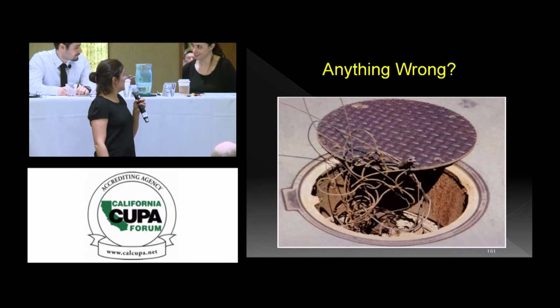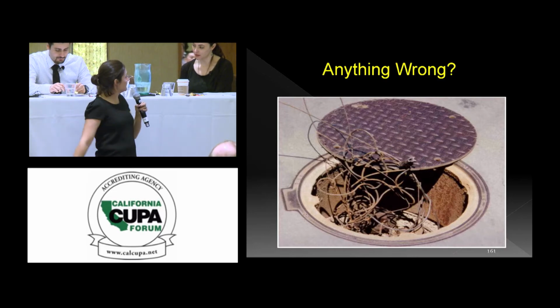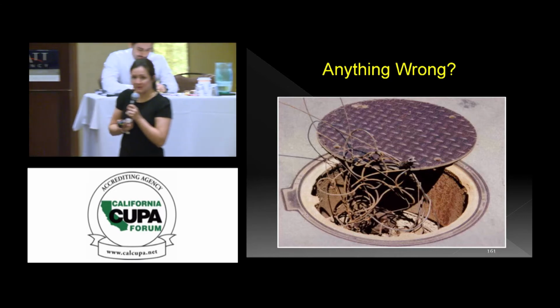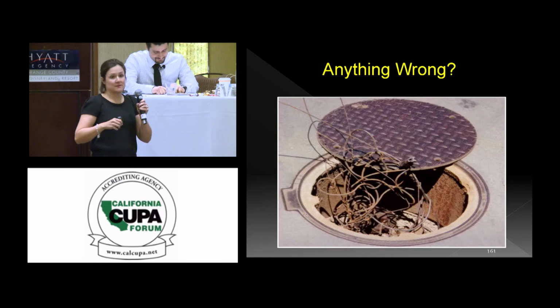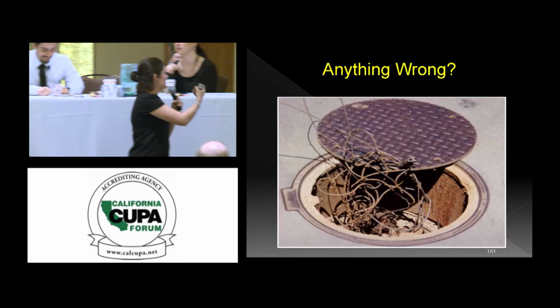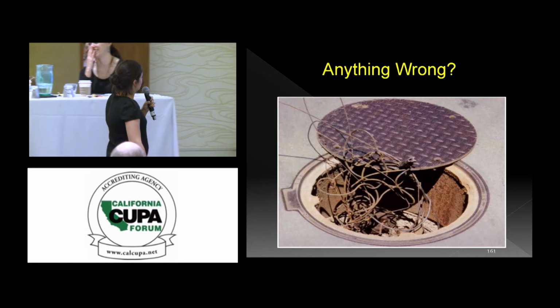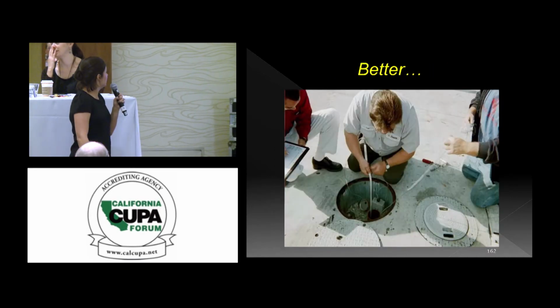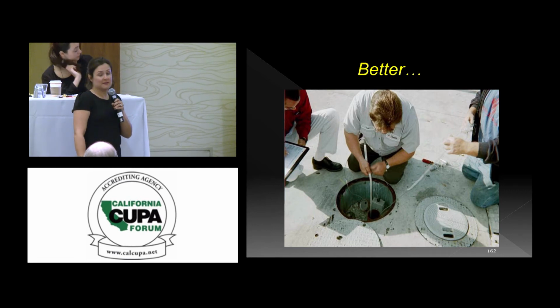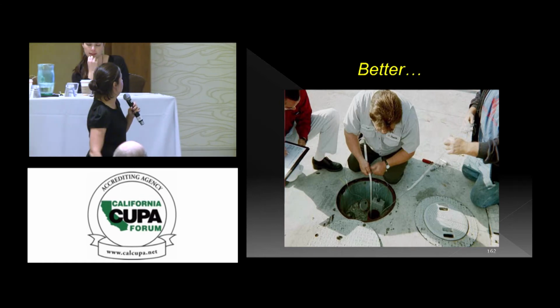And like I said, this is fiberglass tanks that you're going to find this type of monitoring. So here's an example of something that you don't want to see. You see the jumbled cables. You see some fish tape. And for those of you that know, fish tape is kind of like a small rigid steel wire that helps people move the sensor around the tank. So what happens is you can get a mess here and you don't know what's what. But this is what you want to see. You want to be able to move this sensor with ease. You want to be able to take it out, look at it, and do your functional testing. So when it's looking this good, you're in pretty good shape.